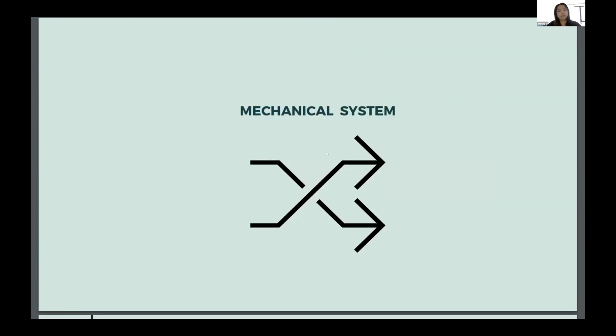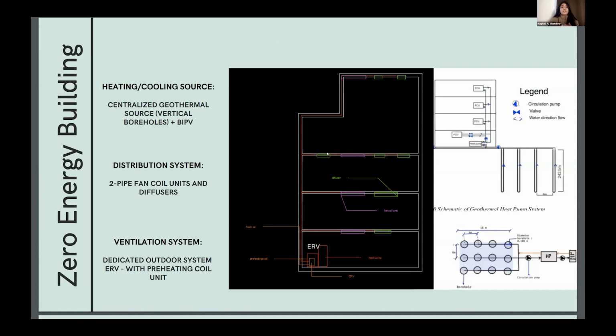Now moving on to the mechanical system, we opted to design a centralized heating and cooling source, choosing to install a vertical closed loop geothermal system equipped with 12 boreholes, each 242 meters deep. This centralized system will supply cooling and heating to the 12 units by installing one individual geothermal heat pump in each unit.